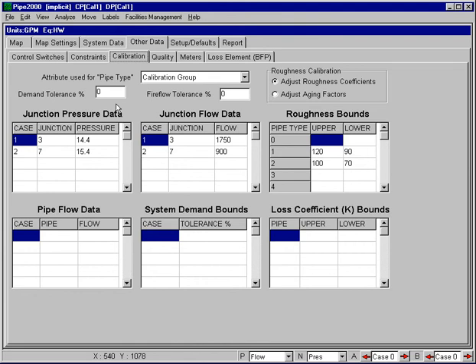This cell is provided to allow the user to specify calibration tolerance associated with the total system demand. When a non-zero value is specified, the calibration algorithm will attempt to make adjustments to the total system demand within the specified tolerance and attempt to decrease the deviation between the observed and model predicted state values, and in this case that would be the pressures. Normally, it will be expected that the tolerance will be zero, that is, the system demand is completely known. However, in some situations, there may be some uncertainty associated with the system demand measurements, and in that case, the uncertainty may be taken into account via this demand tolerance here.